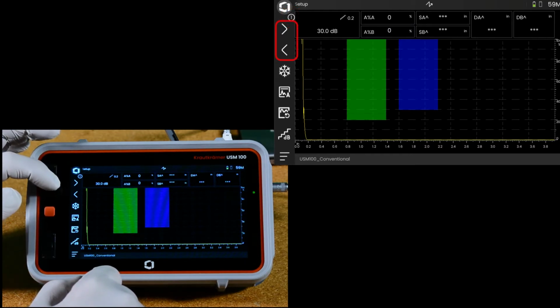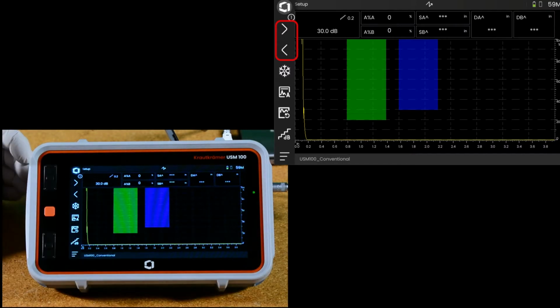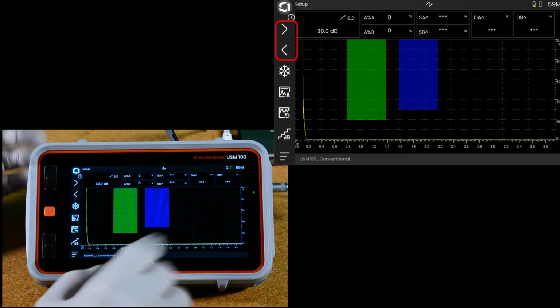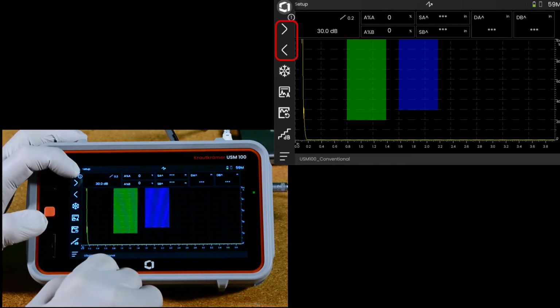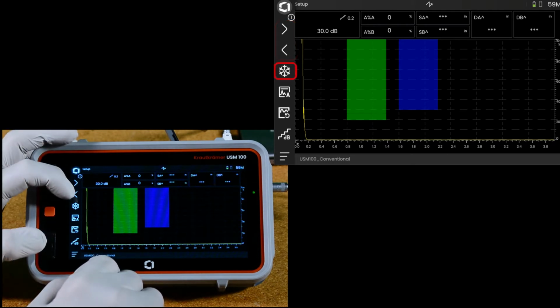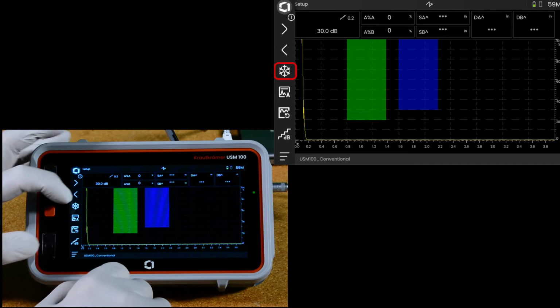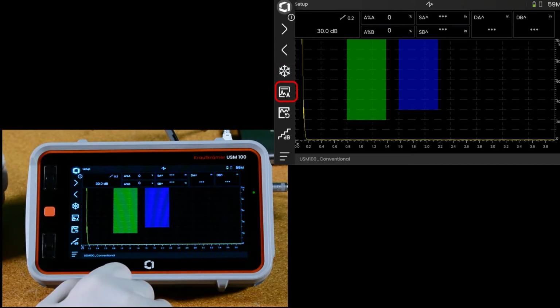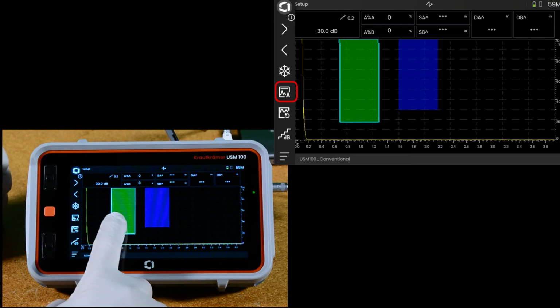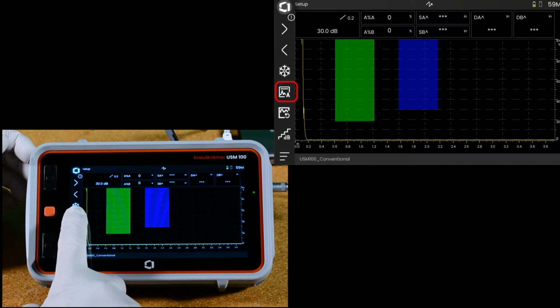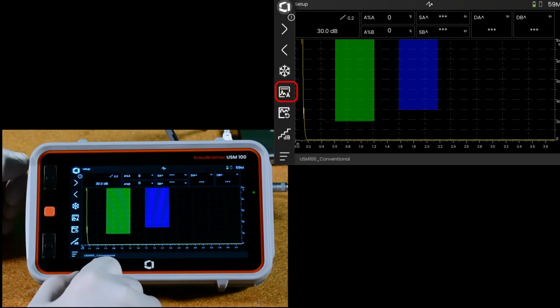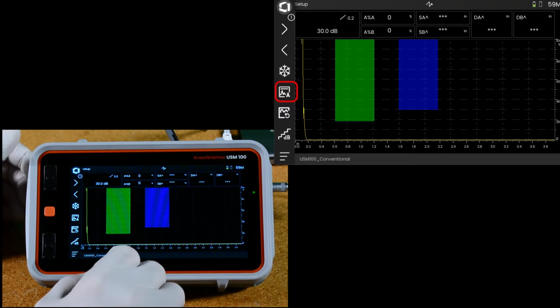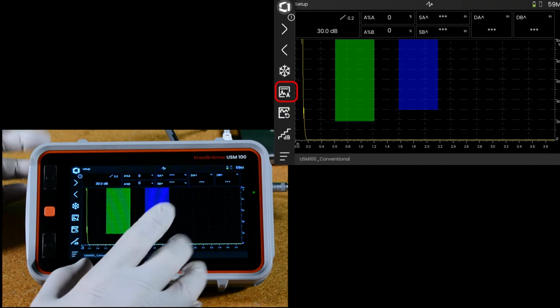Some of the key features of the command bar: the right arrow and left arrow are panel advance and panel back. So each app has multiple panels. You can move through the panels by hitting the forward and back buttons. Right underneath that is the freeze, the snowflake, and Auto 80 is another key feature of this instrument. If you have your gate A over top of a signal, you hit the Auto 80 button, it will adjust the gain automatically to make that 80% screen height. It's actually not always 80. You have the choice of choosing a different amplitude that you would like to have the automatic gain control set to.